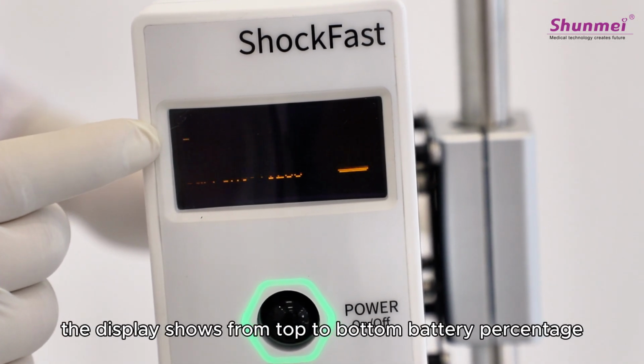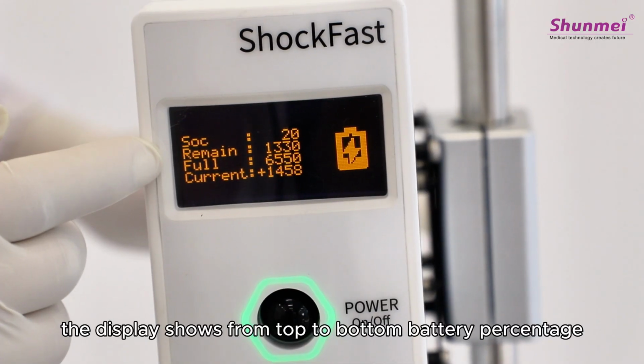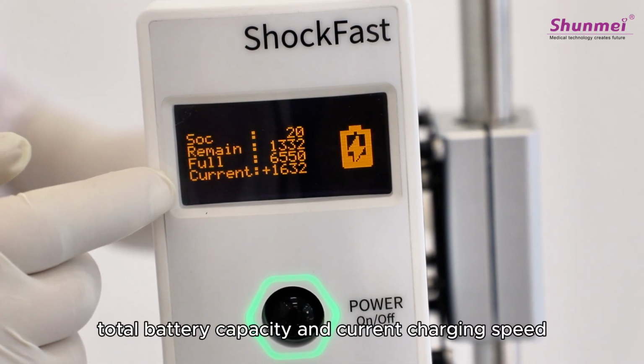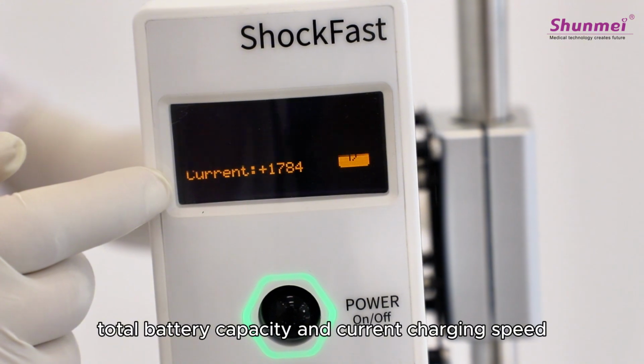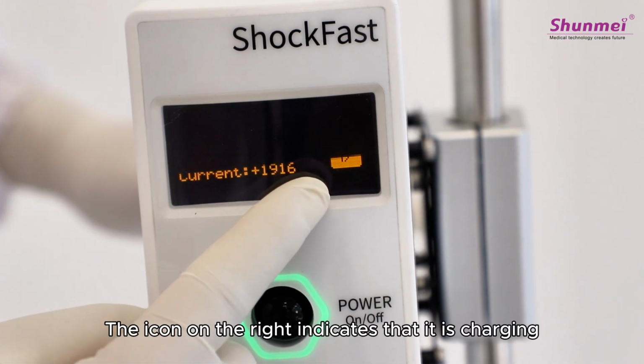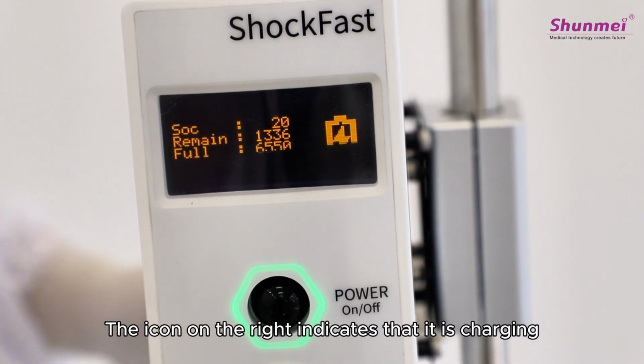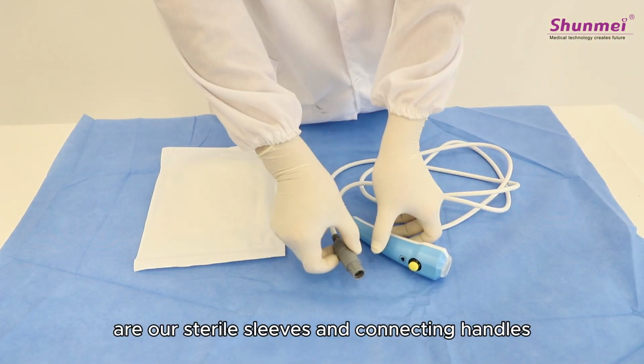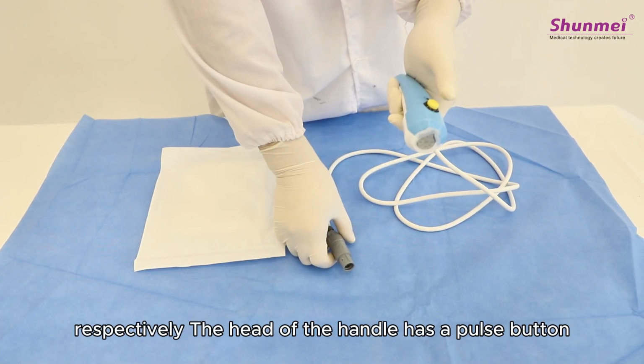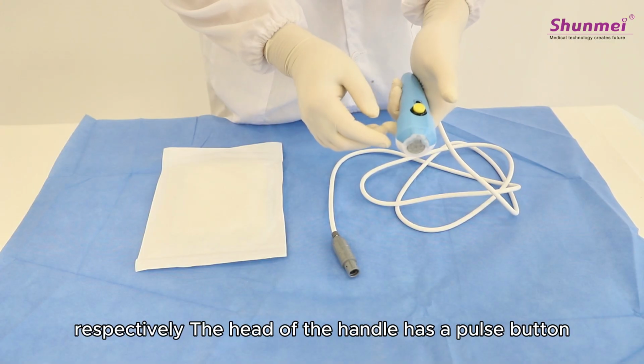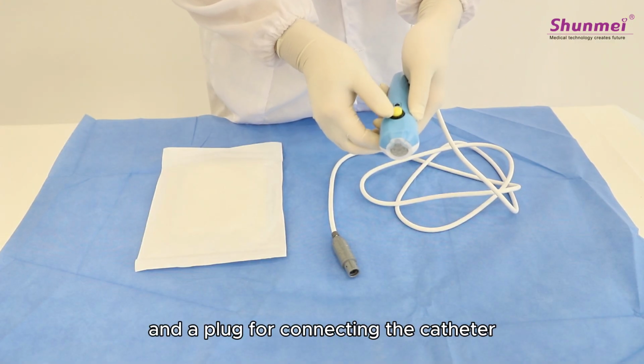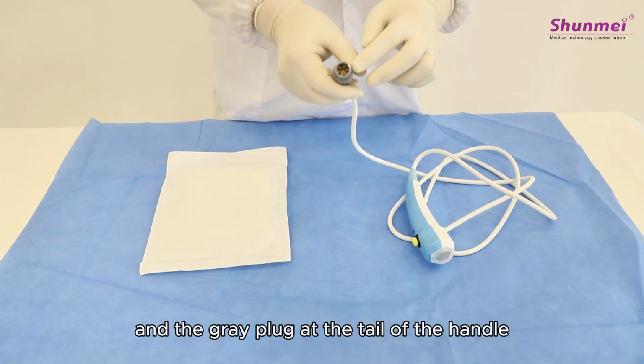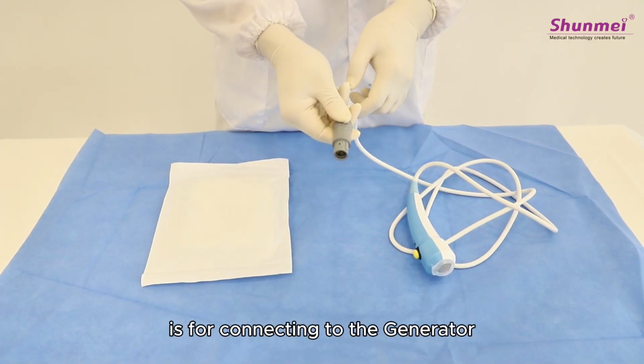After the generator starts charging, the display shows from top to bottom: battery percentage, remaining battery power, total battery capacity, and current charging speed. The icon on the right indicates that it is charging. On the desktop are our sterile sleeves and connecting handles respectively. The head of the handle has a pulse button and a plug for connecting the catheter, and the grey plug at the tail of the handle is for connecting to the generator.